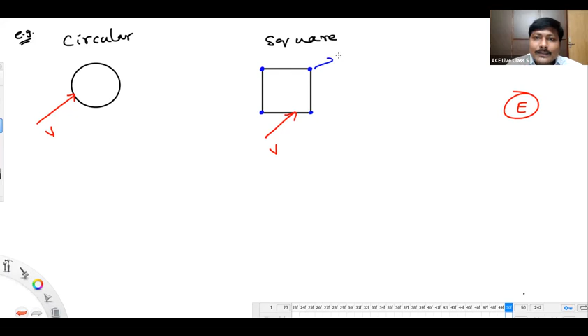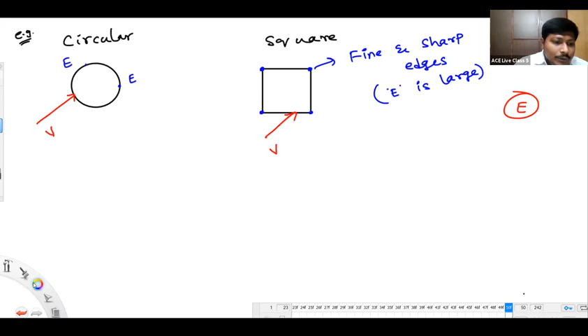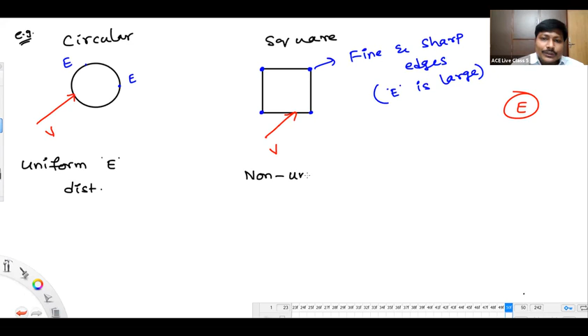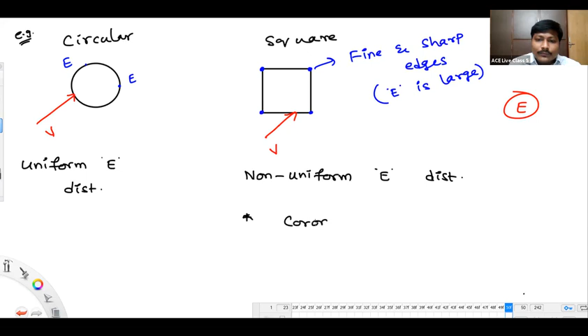But on the circular conductor, you don't find any fine and sharp edges. So the electric field intensity remains the same at all places on this conductor shape. We have a uniform electric field distribution on the circular conductor, but a non-uniform distribution of field on the square conductor. Because of the high electric field intensity at the fine and sharp edges, the possibility of corona will be more on the square conductor compared to the circular. On the circular shape, corona will be less.